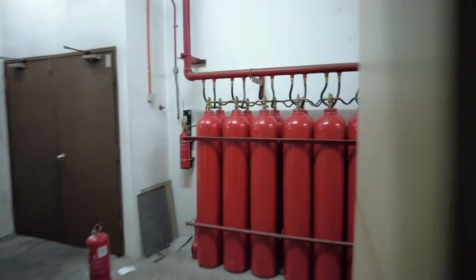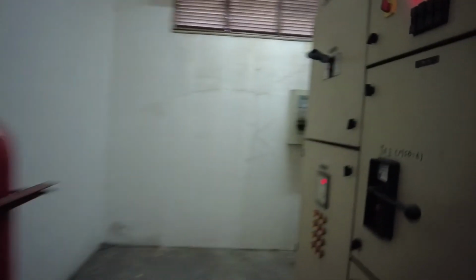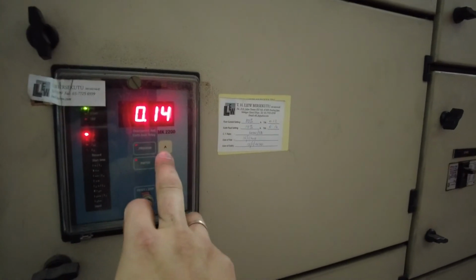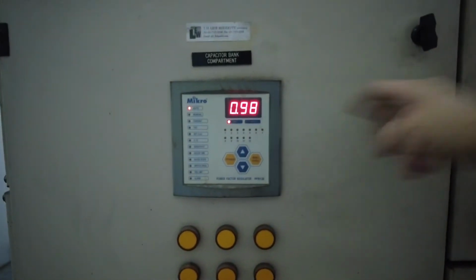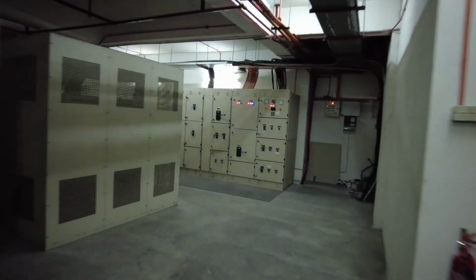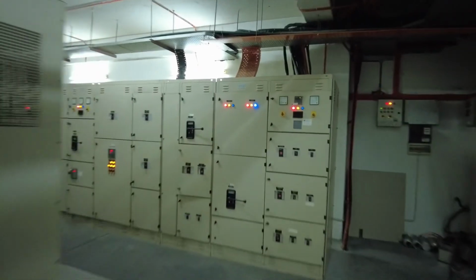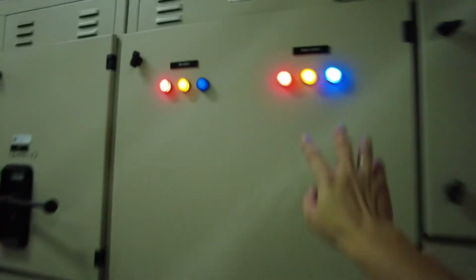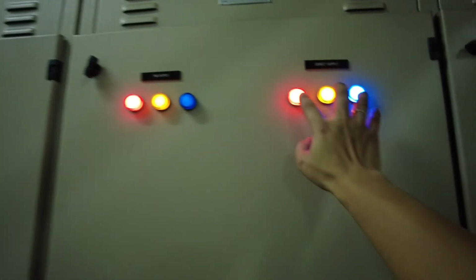And here we have another MSB panel. This is MSB number 6, transformer number 1. 14% load. Overcurrent setting 80%. Power factor 0.98. Let's check inside. No MCCB trip. No cable burn. Here we have the genset still running. After a few minutes, it will stop automatically by itself.